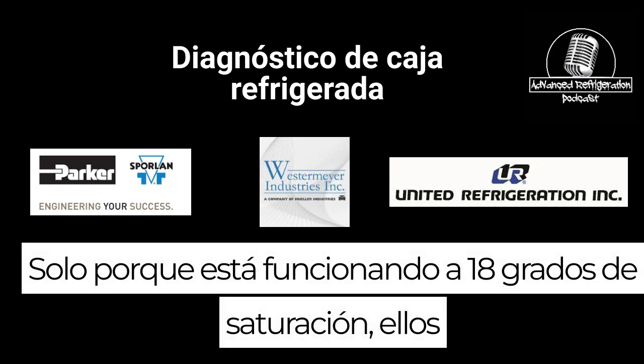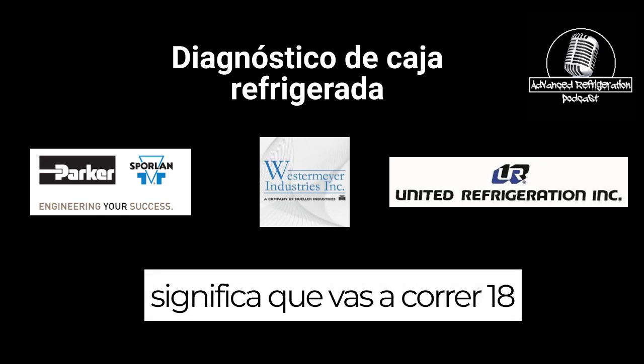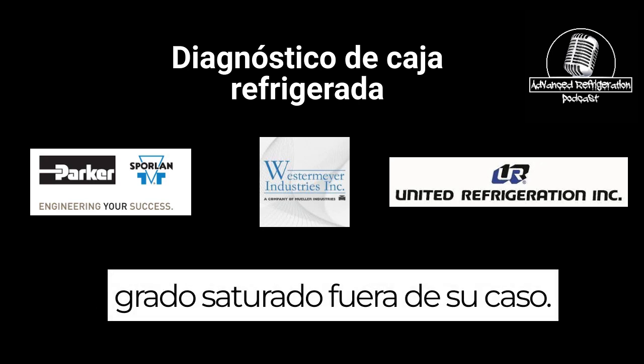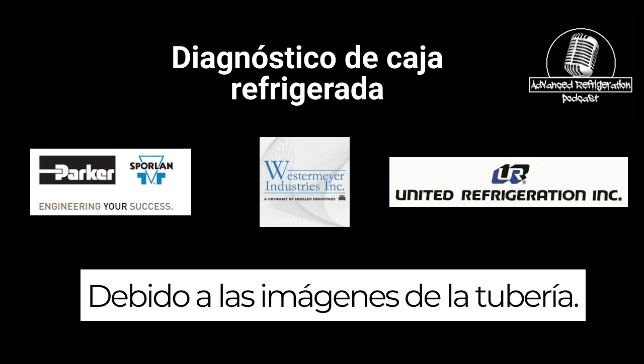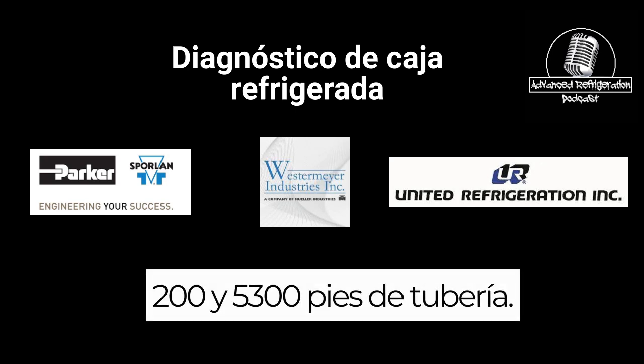Just because you're running 18 degrees saturated doesn't mean that you're going to be running 18 degrees saturated out at your case, because of the footage of pipe. You might have a case that has 250, 300 foot worth of pipe.